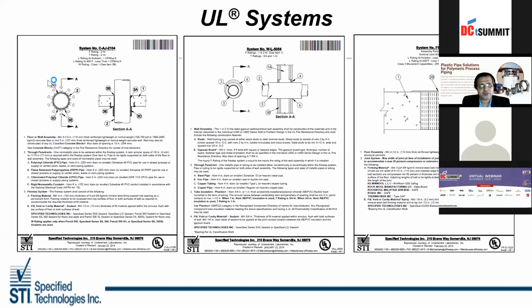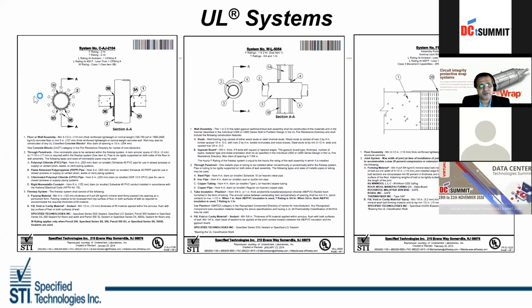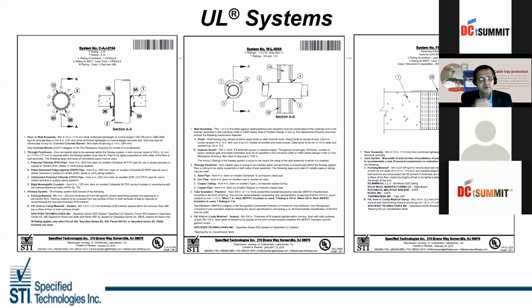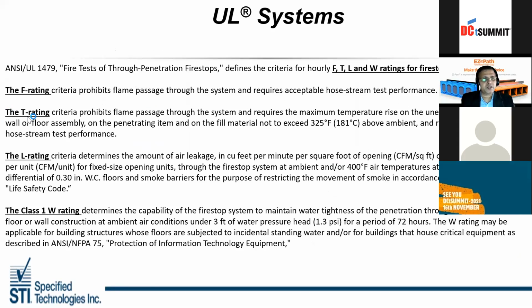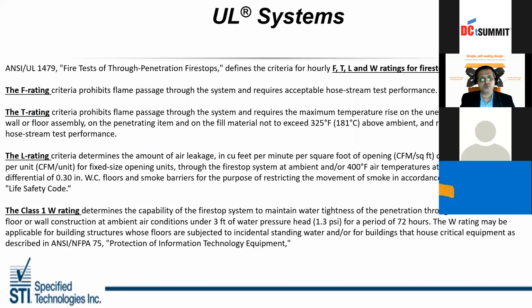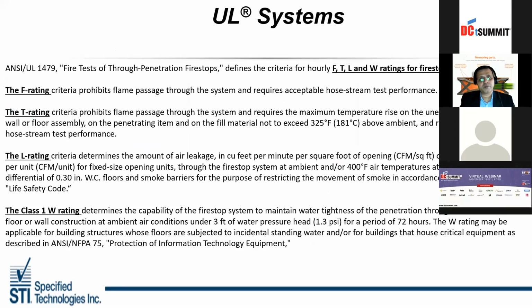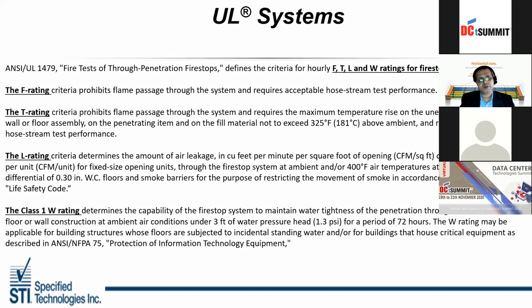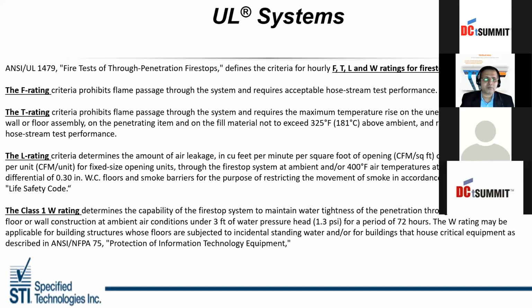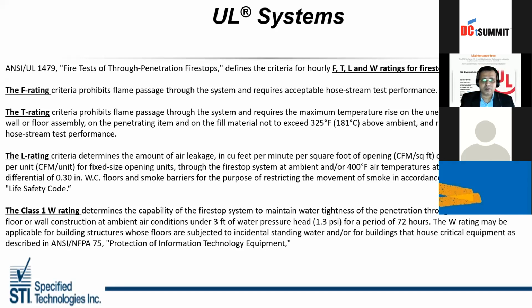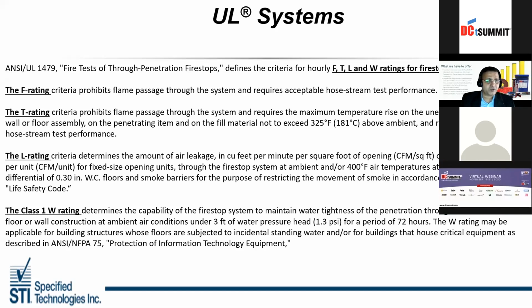So what does a UL tested system define? One is the F rating, fire rating, which normally defines 1, 2, or 3 hours of fire rating. T rating, temperature rating, is normally used for the floor where you have metallic pipes passing through the floor, and there are combustible products kept above the floors. Normally this happens in certain scenarios where the shafts are being closed, and there are some papers or cardboard or thermocol kept in the shafts.